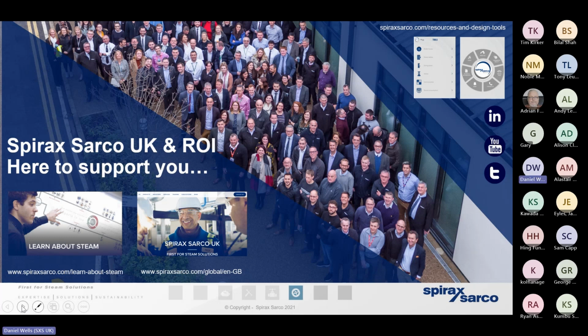Cost of gas. We then need to understand the cost of water. And of course, that's going to vary from one part of the country to another. And we may not necessarily be using water from the mains. We could be using borehole water, river water, reclaimed water. That's going to vary. We're then going to have to chemically condition that water to make it suitable for the boiler. We then need to take into account the pressure and temperature that the boiler operates at. And we also need to give thought to the combustion efficiency of the burner that furnishes the boiler. That's going to vary, probably somewhere between 82 and maybe 86%. But the biggest piece of information of all is the temperature of the water that goes into that boiler. If we know all of those variables, we can calculate our cost of steam.